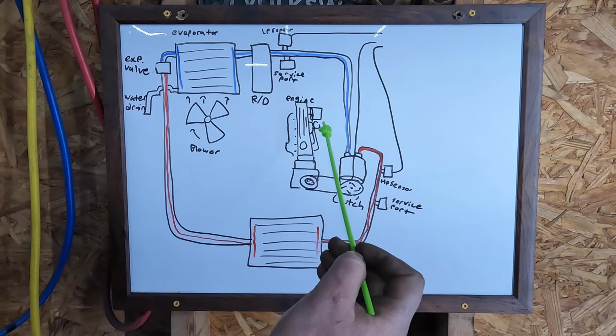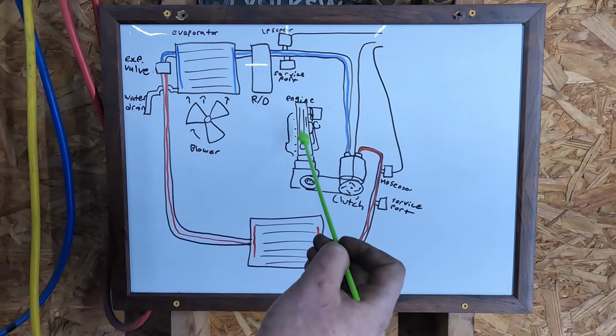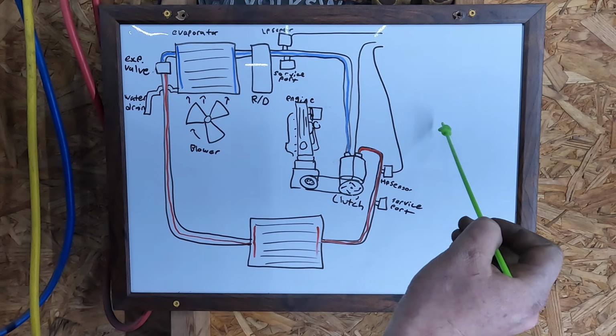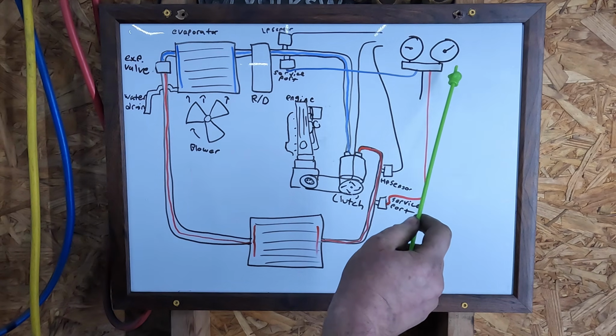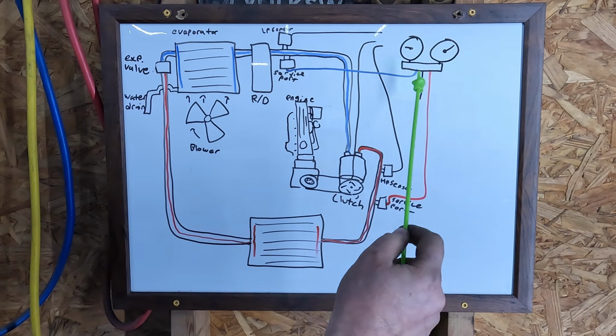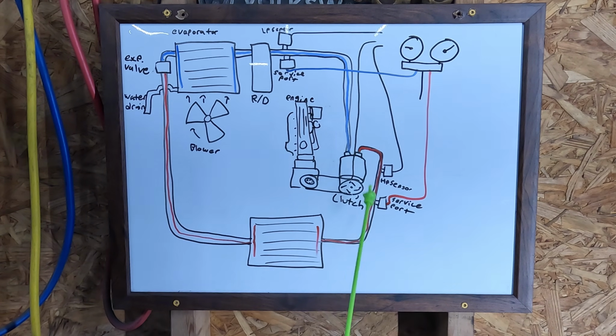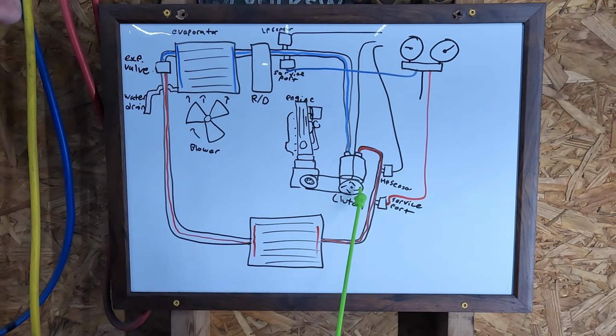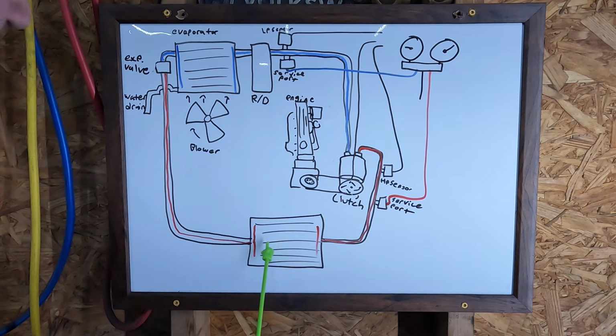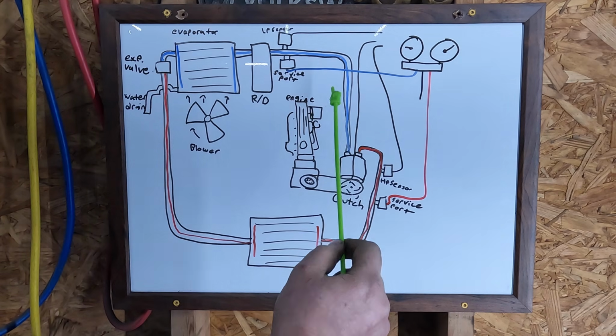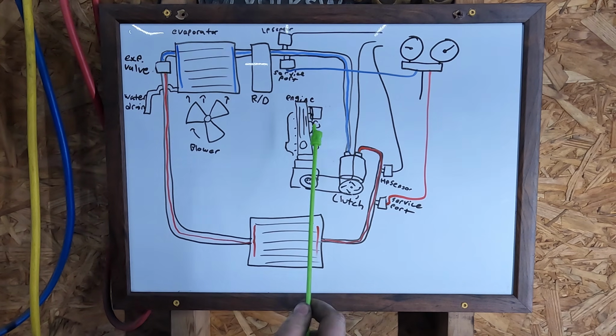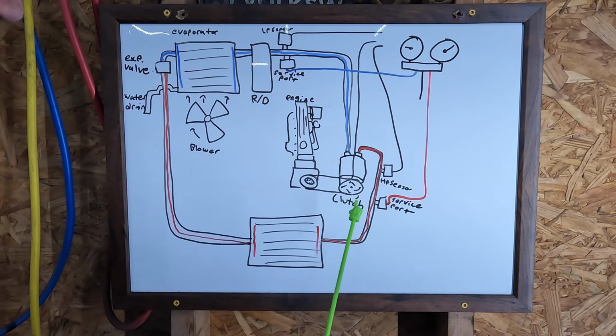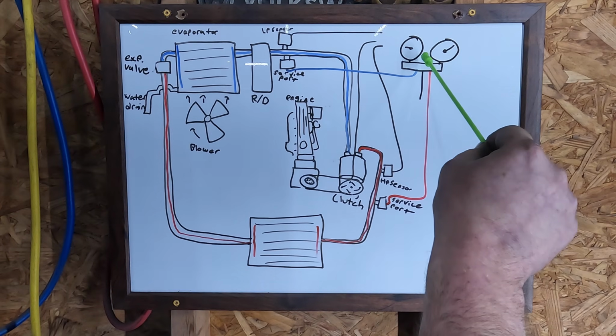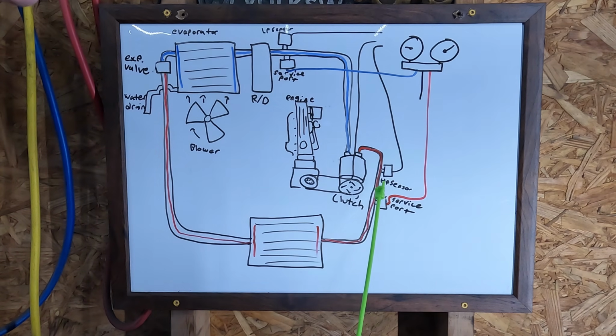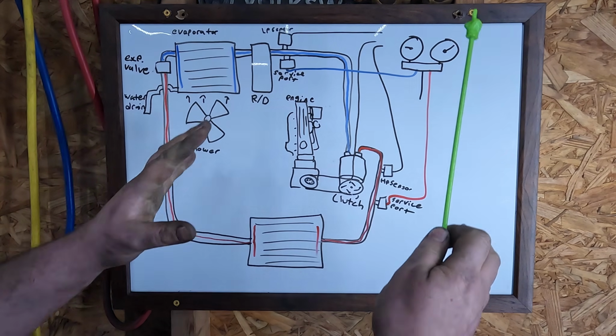So to properly service this system, we need to look at the pressure on both sides of this system. So here we have a manifold gauge, which is just some tubes and some gauges. And that lets us see that the compressor is not only making pressure, but also making suction, because the pressure differential across the expansion valve is what makes all the magic happen to begin with. We'll see this in action later, but just so you're prepared for where the things plug in and what they do.